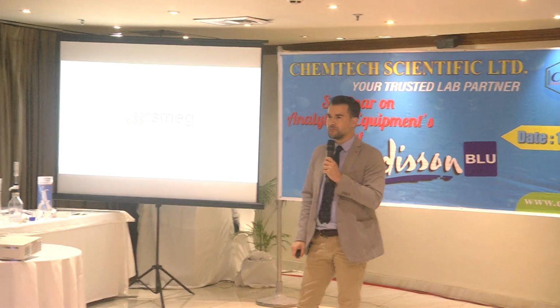And is the detergent specific for your glassware machine? Of course, we have our detergent, and all our 20 pre-installed cycles are validated by Smeg in our laboratories using our detergent. But we are not closed, we are open. You can buy from the local market the detergent that you prefer, that the distributor can offer you. But you have to validate the cycles with that detergent by yourself. We can give you the information regarding the detergent. Generally, the detergents are alkaline, and it should be antifoamy. If you use the correct detergent, you don't need an antifoam. Alkaline detergent and acid neutralizer. This is the standard, but you can add more.